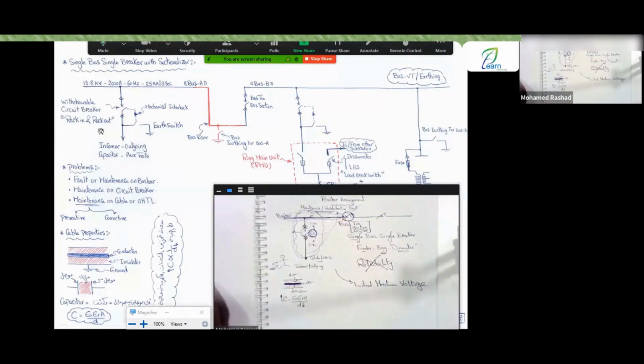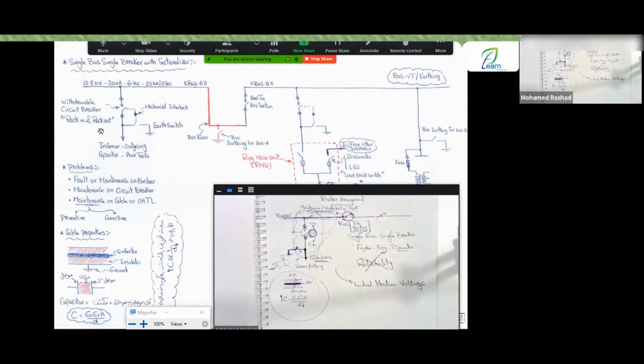On the same bus bar, okay, regarding the cable, Engineer Rashad, you mentioned it has high capacity and is prone to electrical charges. He said, yes, for this cable, you need to install something called a grounding switch. A grounding switch. When you close this grounding switch, what does it do? It discharges, connecting here with the conductor of this cable to discharge the electrical charges into the ground. This ensures that when you are working on the cable, you are safe or completely secure. This is called the grounding switch. That's great, guys. Nice. Okay.